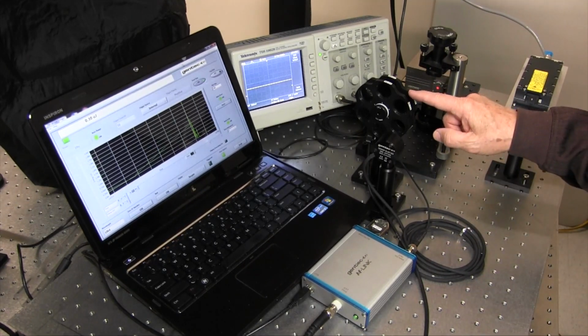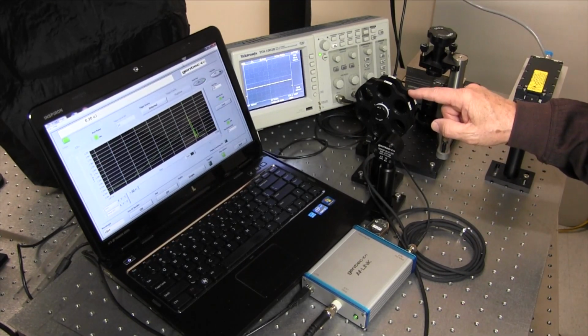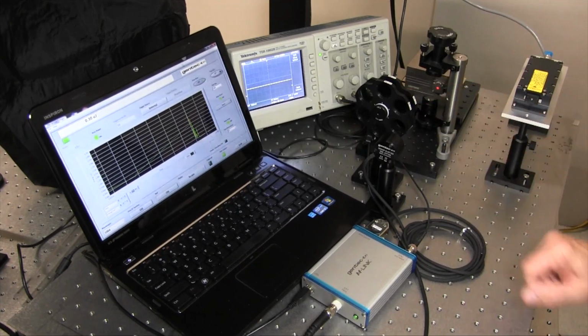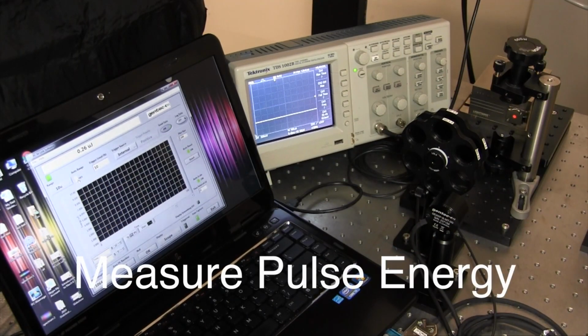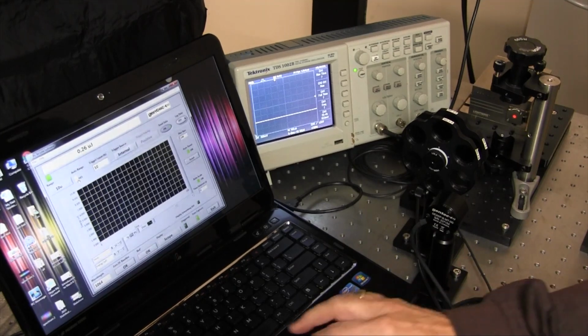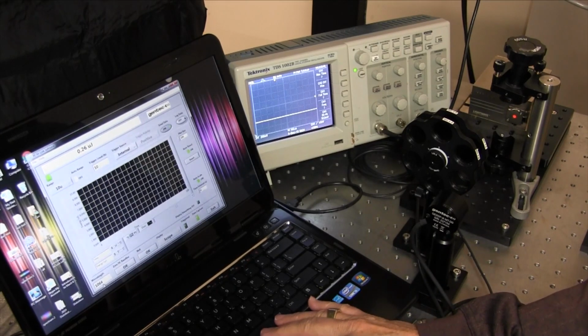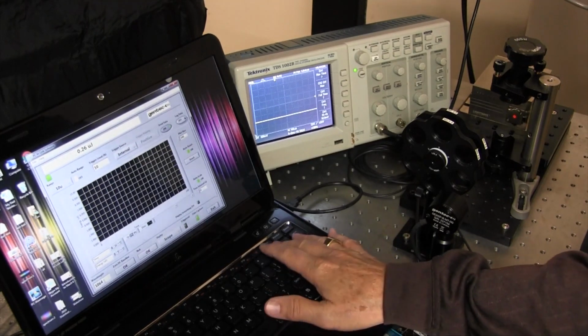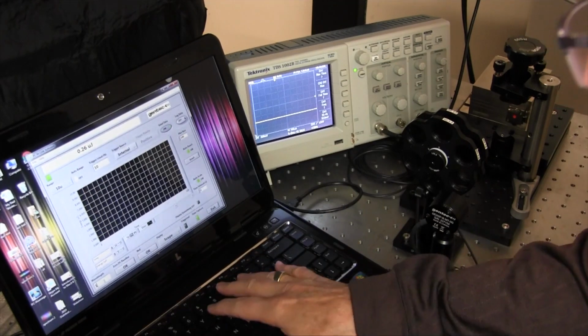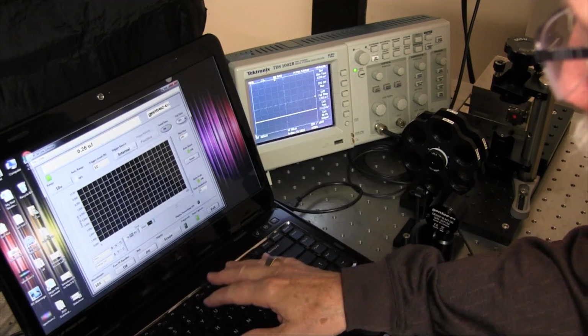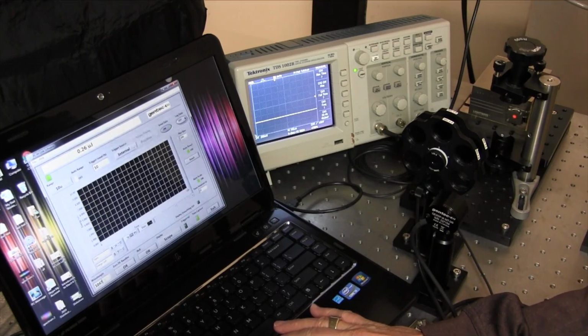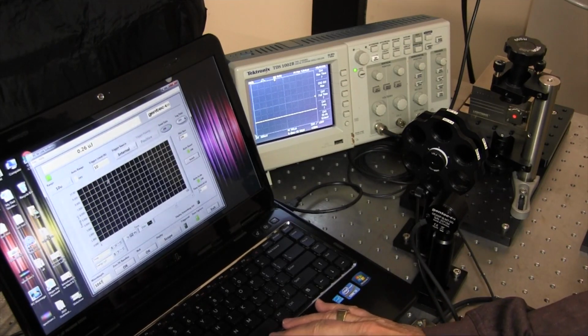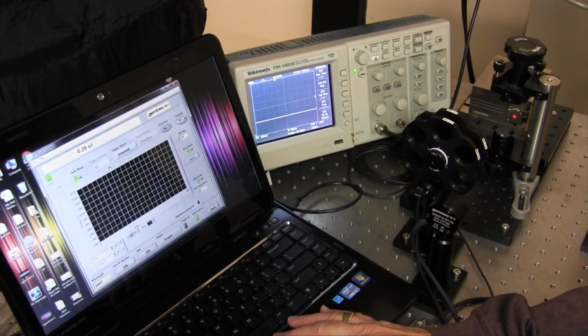I'm taking advantage of an ND filter wheel to set the pulse energy level for demonstration. I'll first adjust the wavelength setting in the M-Link software, make it 1047 nanometers to match the laser wavelength, and then I'll go up here and select auto range. I will leave the instrument set to internal trigger. The default trigger level is about 10%.